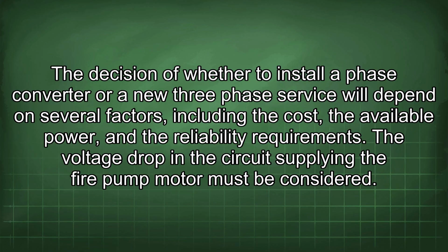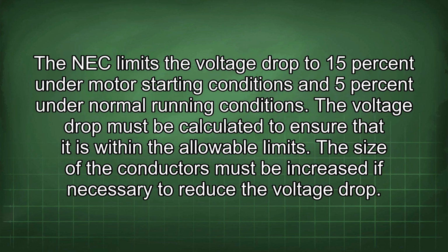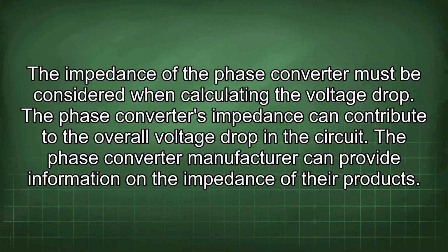The voltage drop in the circuit supplying the fire pump motor must be considered. The NEC limits the voltage drop to 15% under motor starting conditions and 5% under normal running conditions. The voltage drop must be calculated to ensure that it is within the allowable limits. The size of the conductors must be increased if necessary to reduce the voltage drop. The impedance of the phase converter must be considered when calculating the voltage drop. The phase converter's impedance can contribute to the overall voltage drop in the circuit. The phase converter manufacturer can provide information on the impedance of their products.